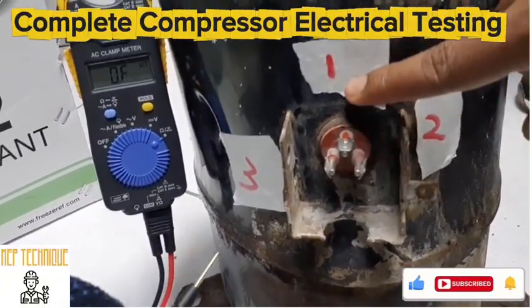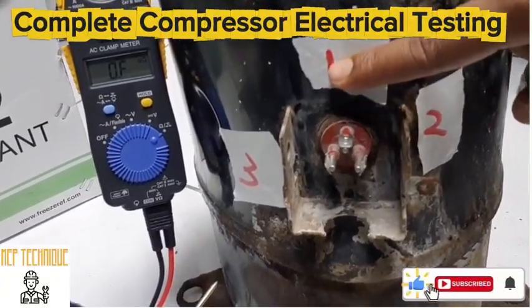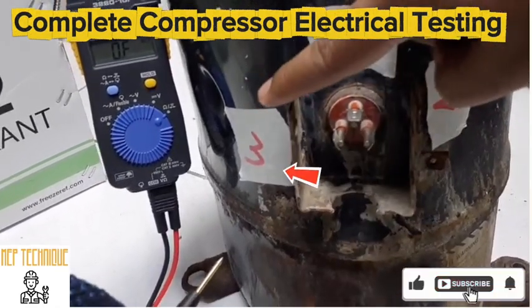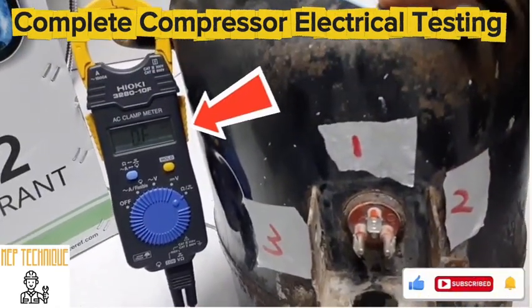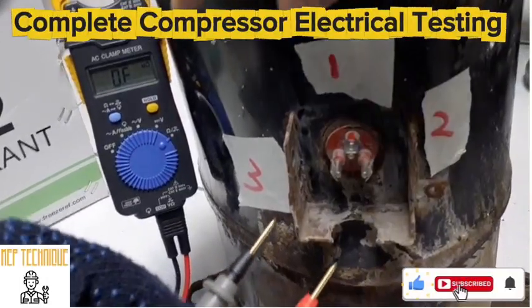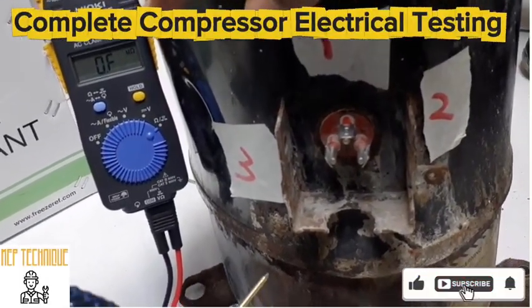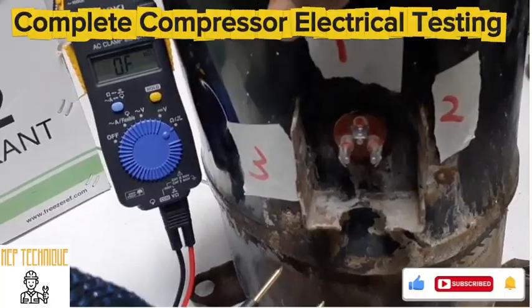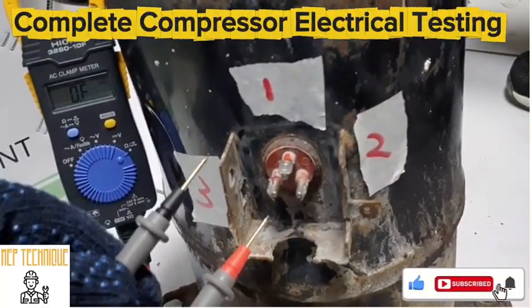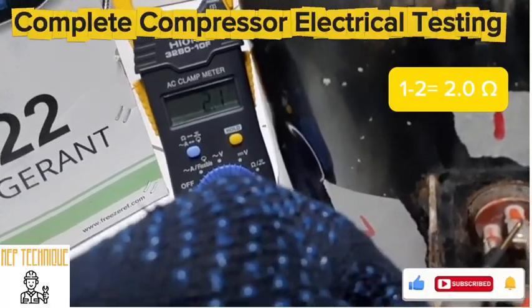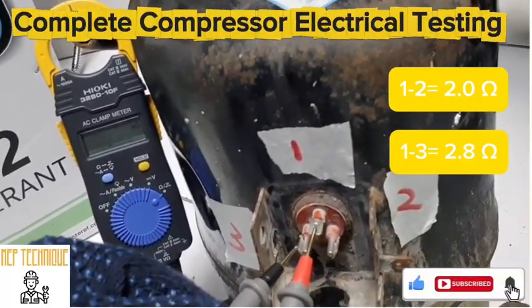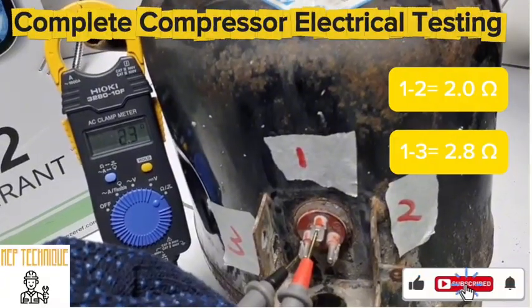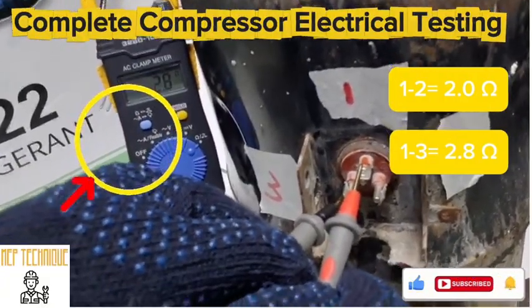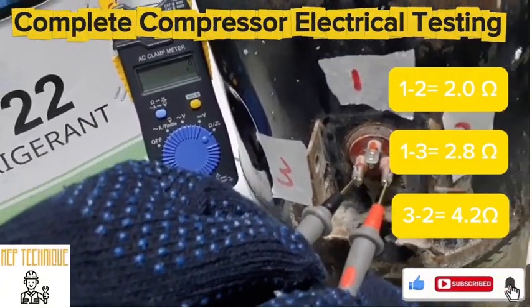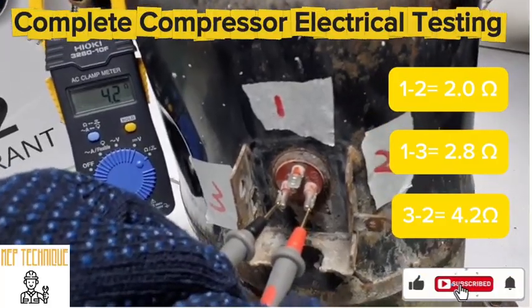We have marked the terminals as 1, 2, 3. We are going to check with a clamp meter. You have to put your clamp meter in resistance or continuity mode to check the resistance value. First check 1 to 2: 2.0. Next 1 to 3: our resistance is 2.8. Then 3 to 2: 4.2.